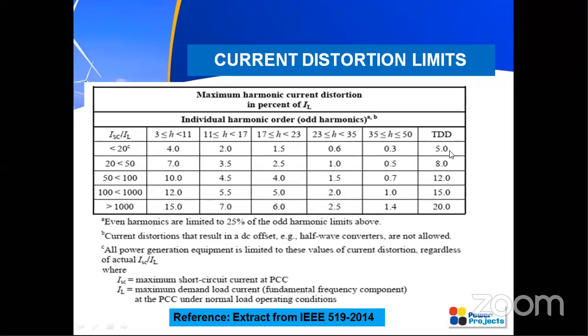Or you can go for another limit such as TDD, total demand distortion. THD is total harmonic distortion, which compares the individual harmonic with the fundamental one. TDD compares your individual harmonics with the load current. So that is the difference between THD and TDD. You can check this also when you go for integration of wind turbines.